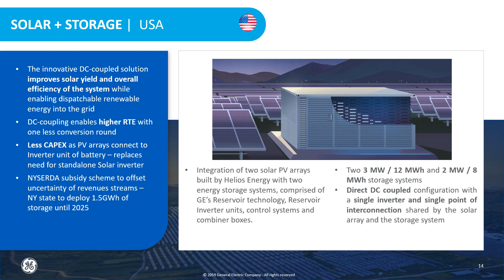GE provided two 4-hour storage systems that are DC coupled to a solar farm, providing peak load and frequency regulation in the New York ISO. In this case, the direct DC coupling enables higher efficiency and also CapEx savings, as a common solar and BESS inverter is used.